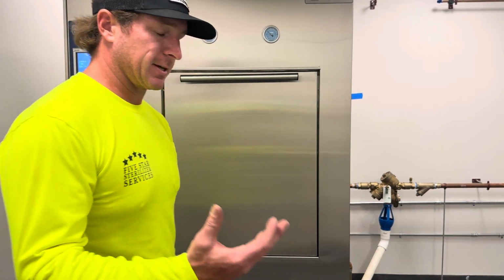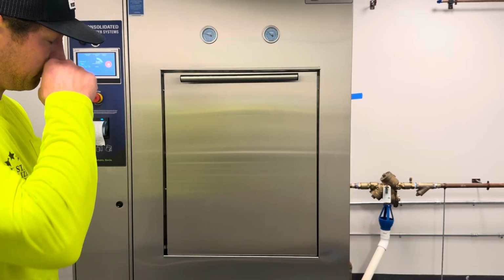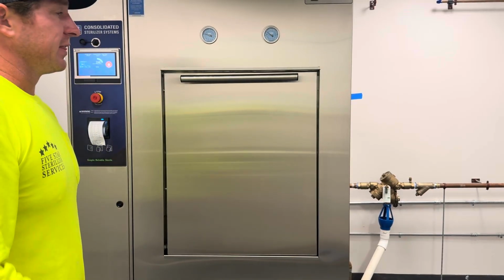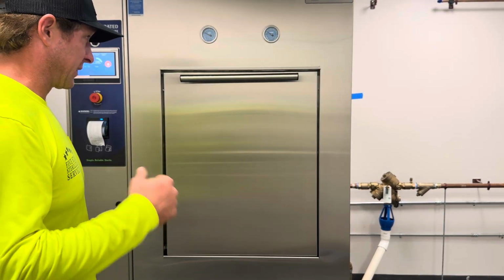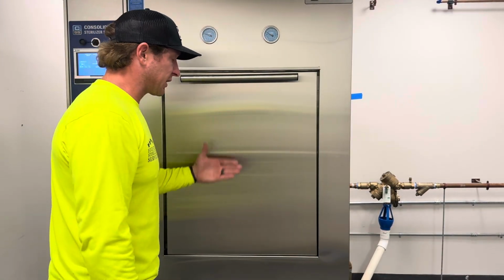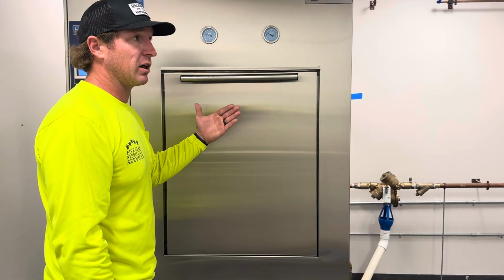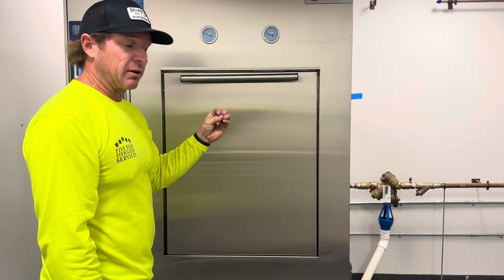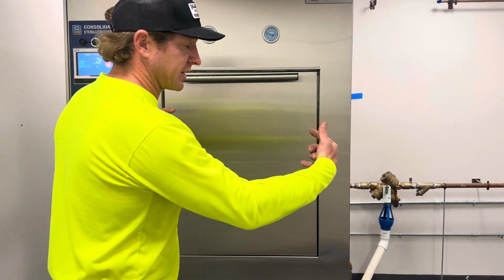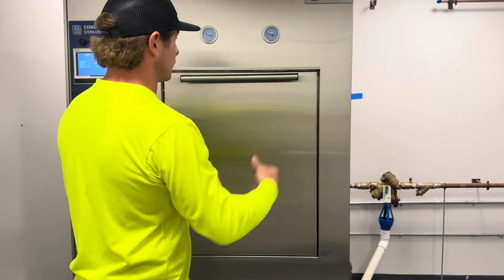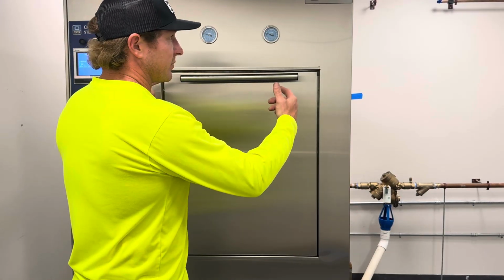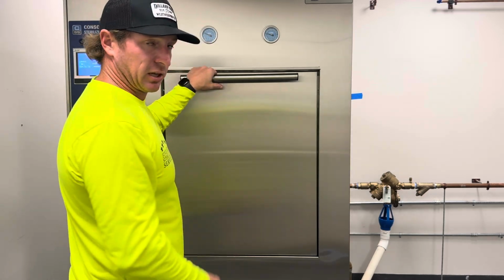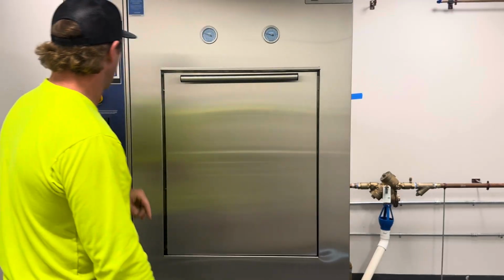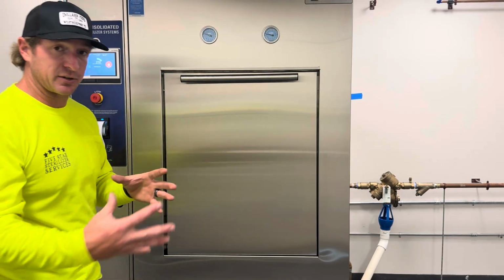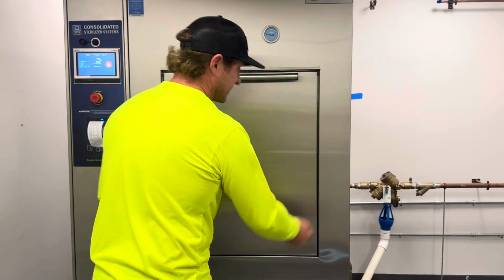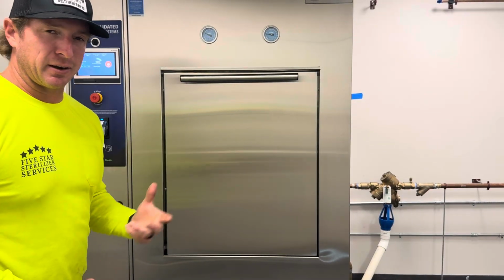After the exhaust phase of the autoclave, or of the total cycle, this will have to suck the door gasket back. So earlier I mentioned this is a Vertiglide door. This is also what we call an active seal sterilizer. What that means is our door gasket, or our door seal, moves once we close the door and press start. Compressed air forces the gasket out to close the door, to close off the chamber. After your exhaust phase, we now have to suck that door gasket back into the machine groove that's around the chamber, and that takes about another minute.